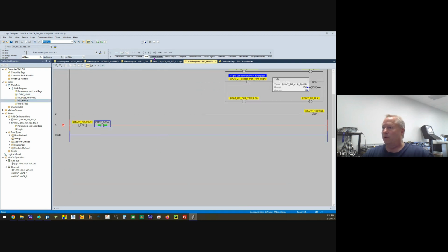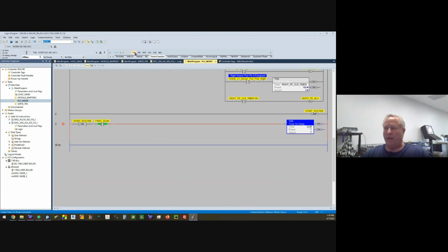And this is where I do, is this mandatory? No. But if it's actually a zone like ZPA, and ZPA does a search routine to look for a stranded load, I also do that in PLC mode if there's a possibility of a stranded load. So that's what we're going to do here.